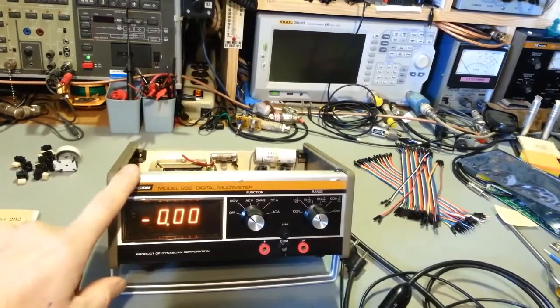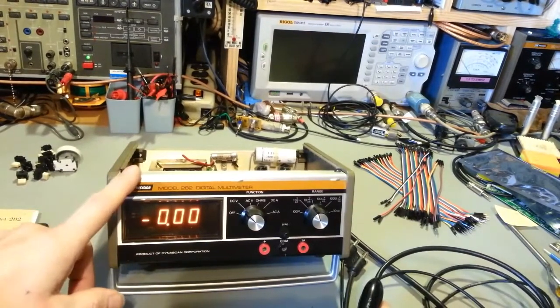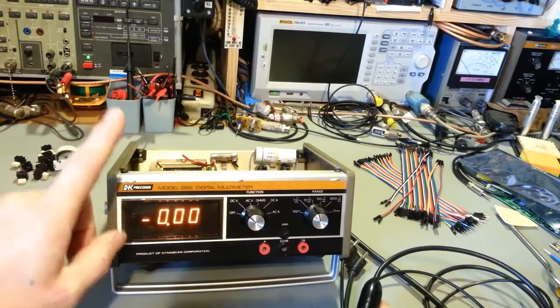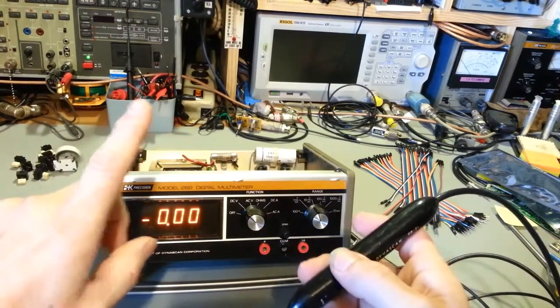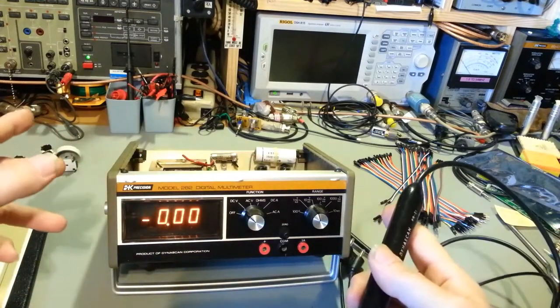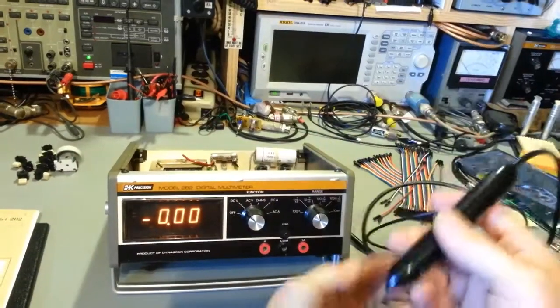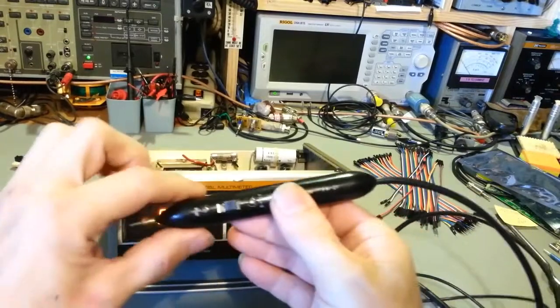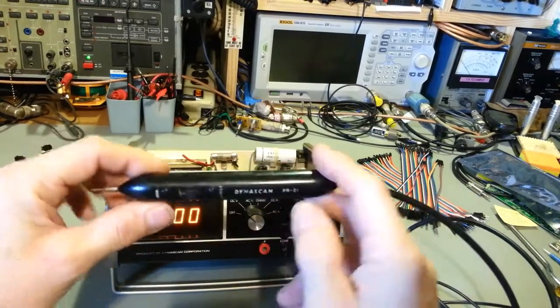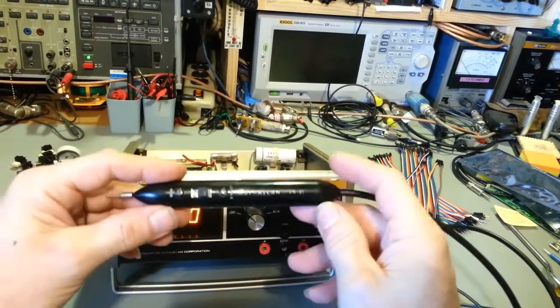This is actually a high input impedance meter. It has a 10 mega ohm input impedance. And if you're having problems with capacitive coupling and whatnot with all this wire and the probe, that's actually why this has this special probe.